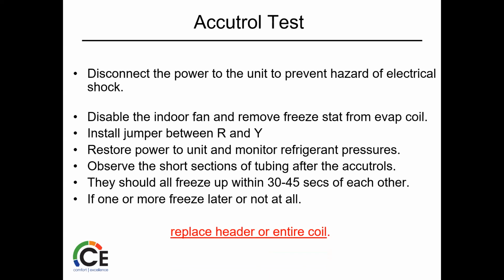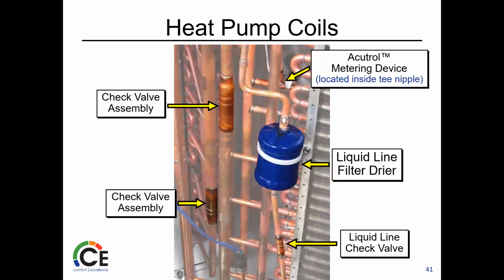And you can do just the header. We can order just the manifold, or some guys just choose to do the entire evap coil. Total preference. Obviously, Carrier Bryant would prefer you just do the manifold, but not a huge deal either way. The warranty won't give you an issue, whichever one you order. So one thing just to remember is when you're replacing that, there are some check valves in that assembly. We just want to make sure that those are there.